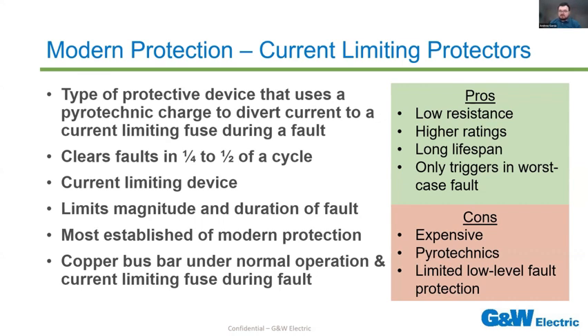They do use pyrotechnics, which is a concern that people have when using these devices. However, the pyrotechnic blast is completely and safely contained within the device itself. There's no additional hazard exposed to workers, but that is something to keep in mind. And ultimately, because this is used as a backup device, it is not a low-level fault protection device. You're not going to be able to use this to clear low-level faults from your system. You need to rely on your regular protective devices in your system to accomplish that.